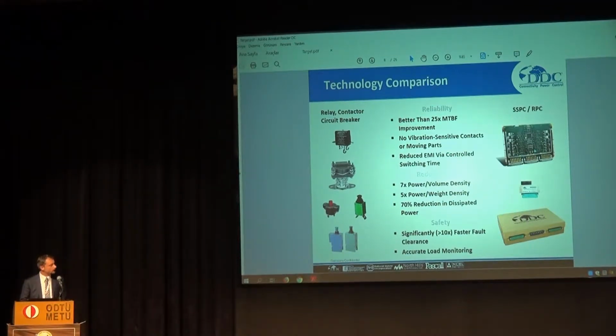Also, the safety aspect. It's significantly faster in terms of fault clearance. Also significantly faster in the reaction time if a channel needs to be tripped or opened. It's faster than a mechanical circuit breaker, and it has a more accurate load monitoring, which you can hardly achieve with a mechanical circuit breaker. You can do it with an electronic device quite easily, and monitor the load, so the current, voltage, temperature of your load, in order to determine the health of your load with the solid-state power controller.